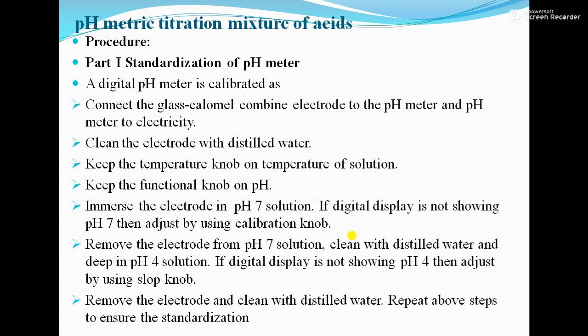If the meter shows pH 7 it is fine; otherwise, use the calibration knob to set it. Then remove the electrode, clean with distilled water, and immerse it in pH 4 solution. If the display does not show pH 4, adjust using the slope knob. For pH 7 use the calibration knob; for pH 4 use the slope knob. Finally, remove the electrode, clean with distilled water, and repeat the above steps to ensure standardization.